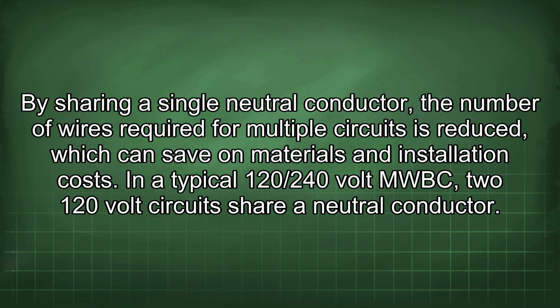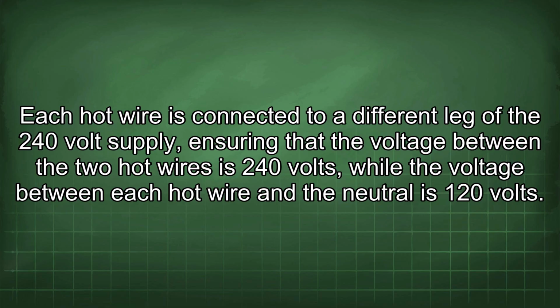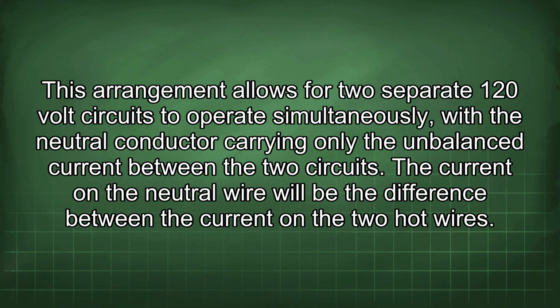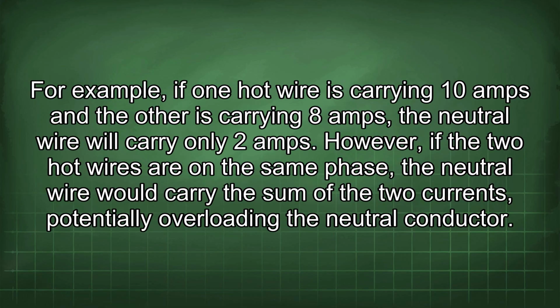In a typical 120/240 volt MWBC, two 120 volt circuits share a neutral conductor. Each hot wire is connected to a different leg of the 240 volt supply, ensuring that the voltage between the two hot wires is 240 volts, while the voltage between each hot wire and the neutral is 120 volts. This arrangement allows for two separate 120-volt circuits to operate simultaneously, with the neutral conductor carrying only the unbalanced current between the two circuits. The current on the neutral wire will be the difference between the current on the two hot wires. For example, if one hot wire is carrying 10 amps and the other is carrying 8 amps, the neutral wire will carry only 2 amps.